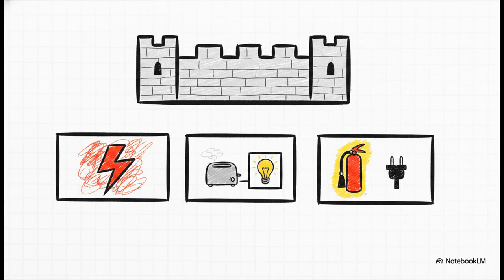Second, it minimizes inconvenience. We set things up logically so that if, say, your toaster shorts out in the kitchen, it only trips the power to the sockets. You aren't left standing completely in the dark because your lighting circuit is entirely separate. And finally, we absolutely must segregate safety services, like emergency lighting or fire pumps, from the general wiring. Because if the regular power goes down, that life-saving equipment still needs to run.